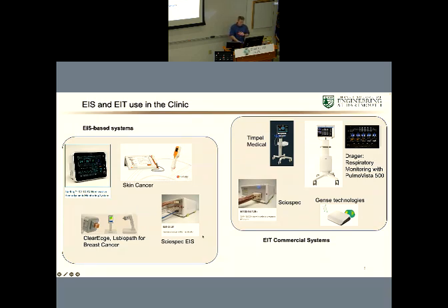And on the EIT side, it's pretty mature, with commercial companies making EIT for ventilation applications. It's bigger in Europe, but for monitoring ventilation on ICU patients, we'll strap one belt around people's chests, and then in real time you'll see the air filling and emptying of the lungs, and they can monitor if the lungs are recruiting properly, front to back, side to side, and you can often match the positive end-expiratory pressure for tuning ventilation settings.